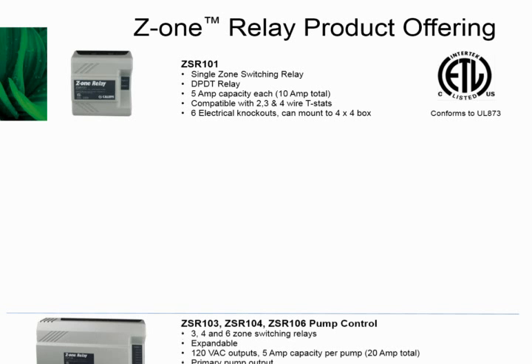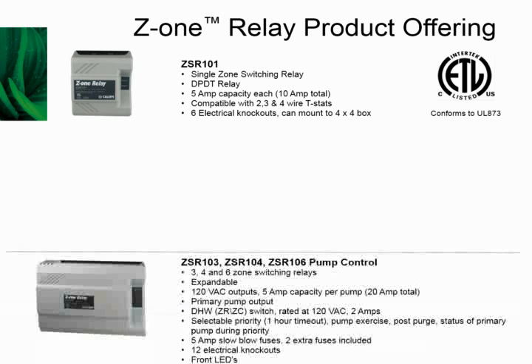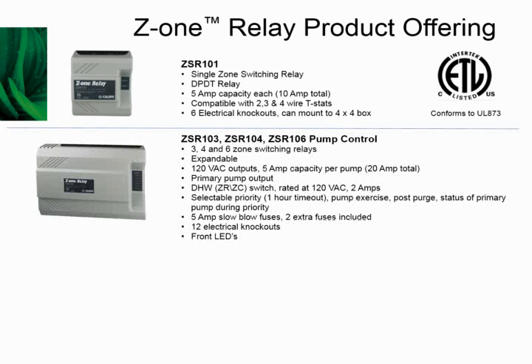The next member of the family is basically the MultiZone pump control. So it's our ZSR 103 through 106. We offer it in a 3, 4, and 6 zone model. The base unit, they're expandable, and they're expandable without limitation as well. So you can daisy chain as many of these units together as you would like. What we output is 120 volts AC to the pumps. We're not just providing a switch, but we're providing the voltage output. There's a 5 amp capacity for each pump with a 20 amp total.